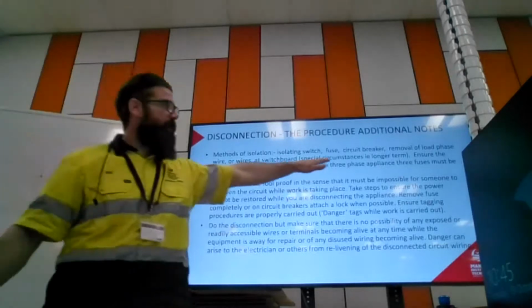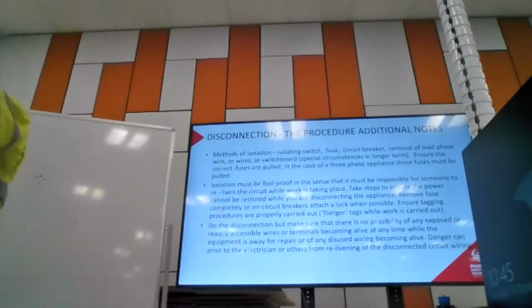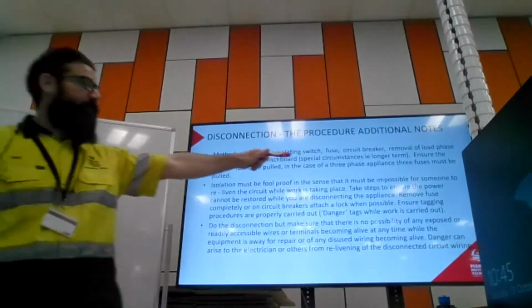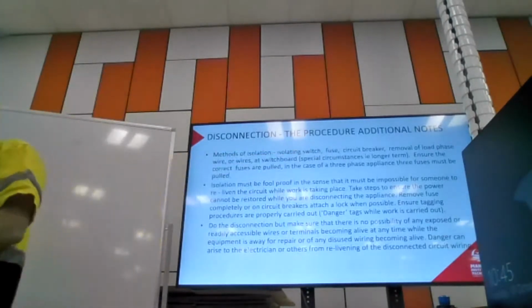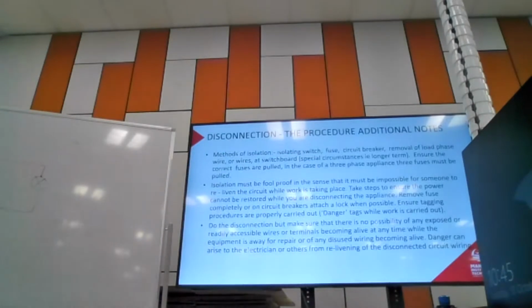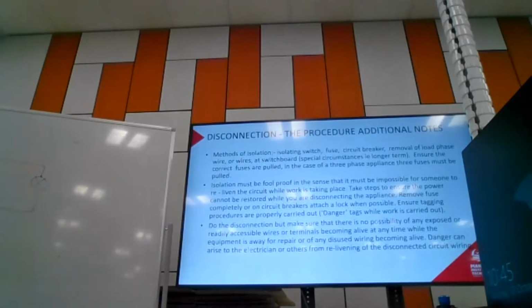Generally in special circumstances, like a longer term disconnection, you might pull that wire out because you're going to leave it disconnected forever or whatever. In the case of a three-phase appliance, we make sure we pull all three fuses. I've done that before too - that's one case where I got a shock because I didn't pull out the right fuses and only tested one of the phases. I think I've talked about this before - the other two phases were still live.